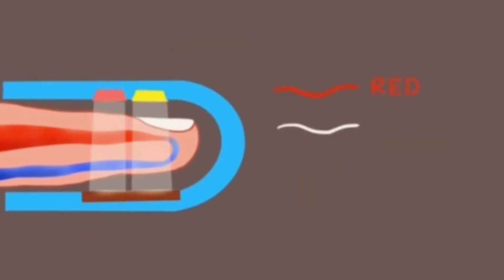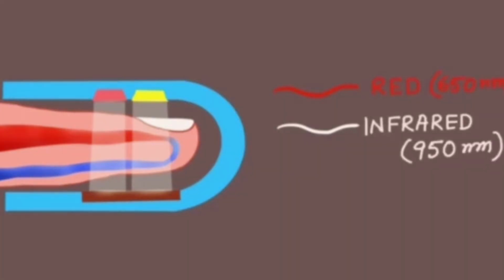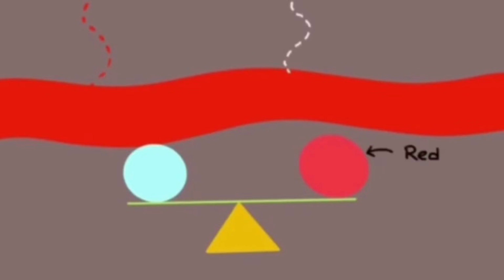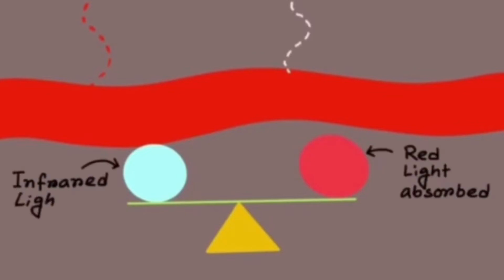Now, a pulse oximeter emits two types of light. One is red light with a wavelength of 650 nanometers and the other is infrared light with 950 nanometers. The pulse oximeter works out the oxygen saturation by comparing how much red light and infrared light is absorbed by blood. Depending on the amount of oxyhemoglobin and deoxyhemoglobin present in the blood, the ratio of the amount of red light absorbed compared to the amount of infrared light absorbed changes. The pulse oximeter can then work out oxygen saturation.